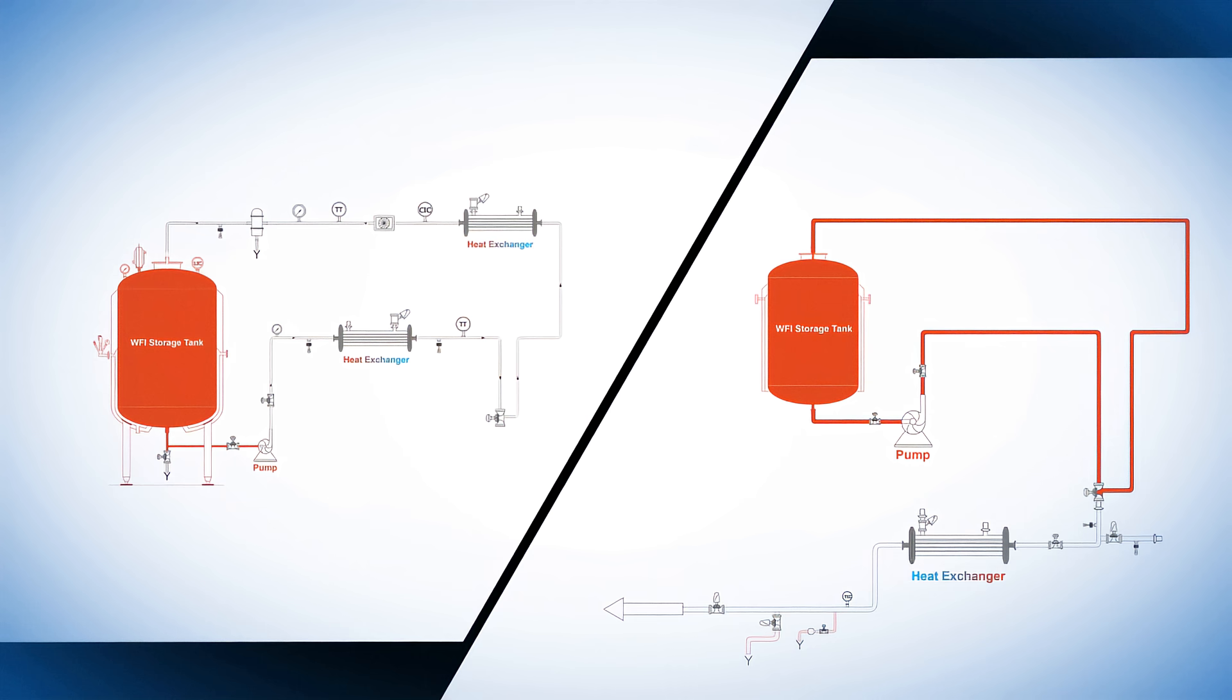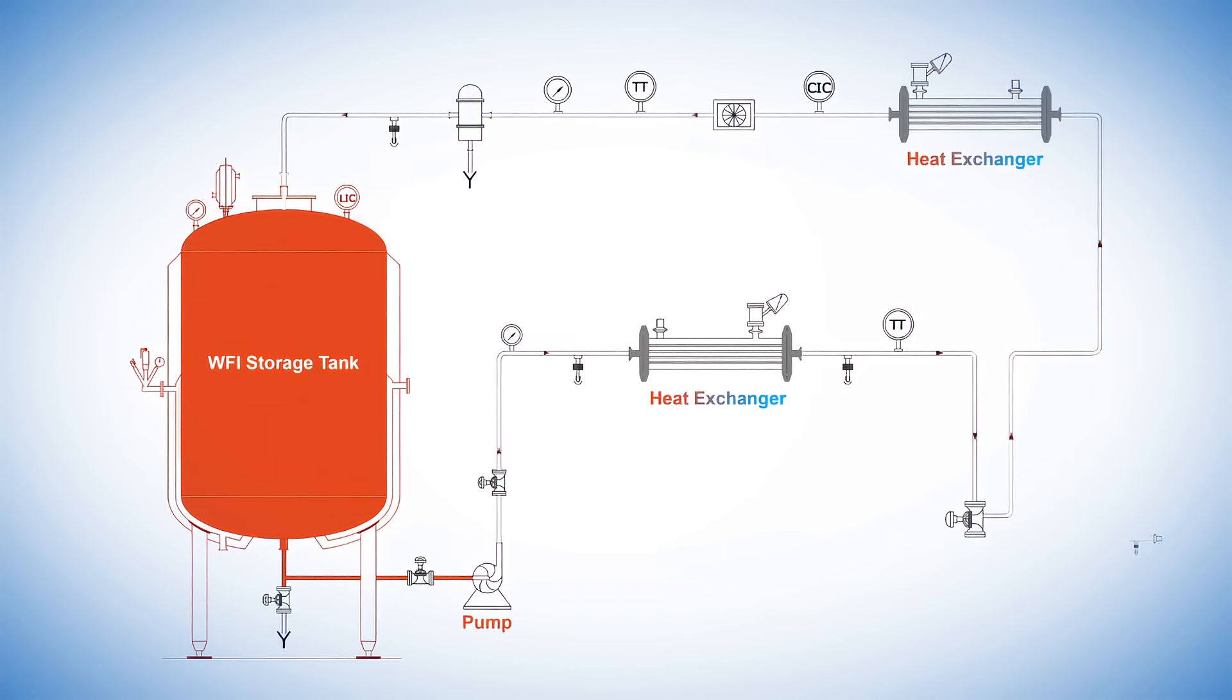There are various methods used in the industry to provide this cooled water. In one method, hot purified water from a stainless steel storage tank is cooled using an inline heat exchanger upstream of the dispensing point. Any water returned to the storage tank is then reheated with a second heat exchanger on its way back.